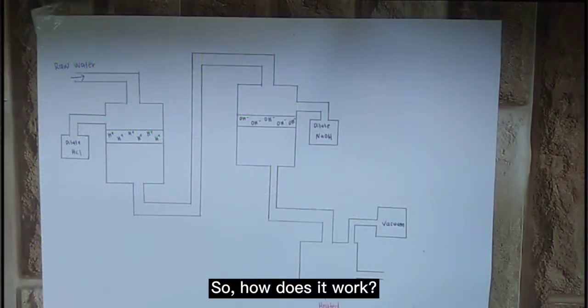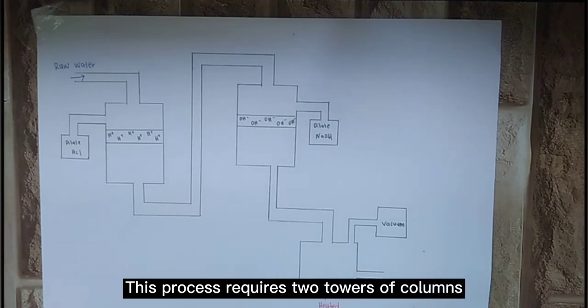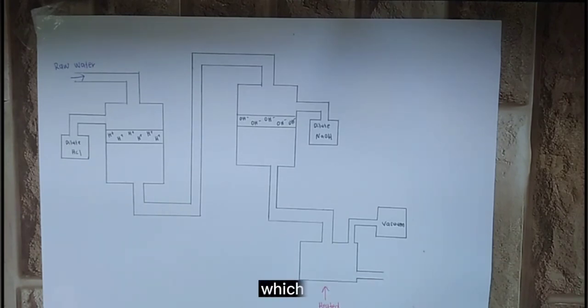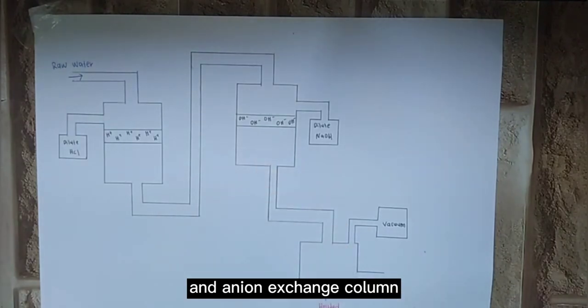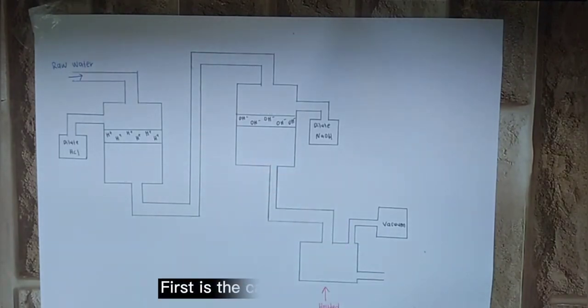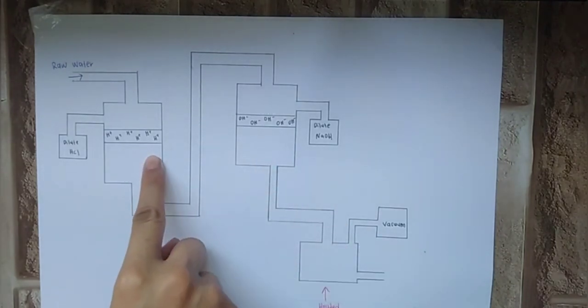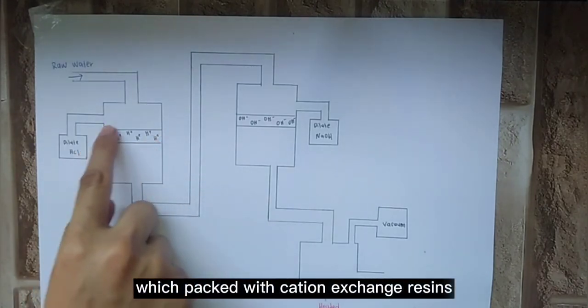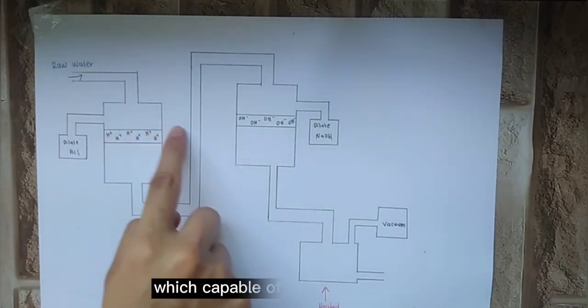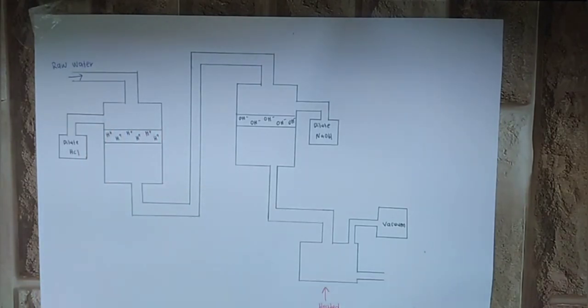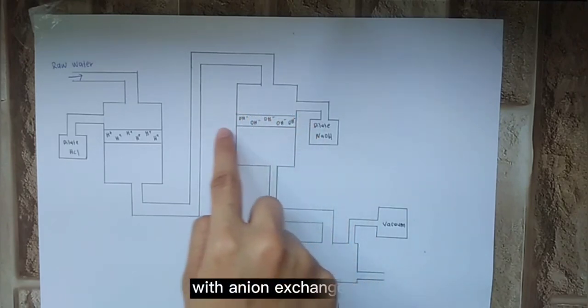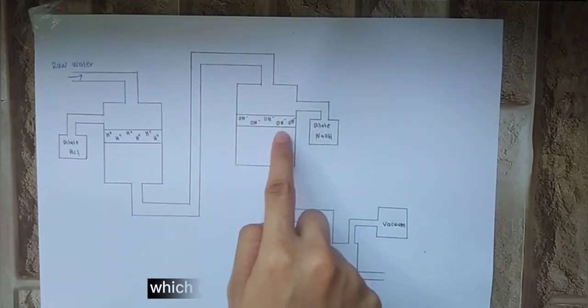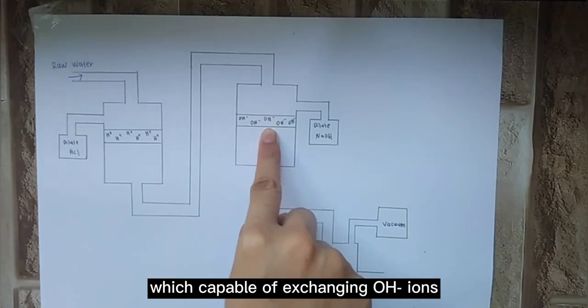So, how does it work? This process requires two towers or columns: a cation exchange column and an anion exchange column. The cation exchange column is packed with cation exchange resins capable of exchanging H-plus ions. The anion exchange column is packed with anion exchange resins capable of exchanging OH-minus ions.